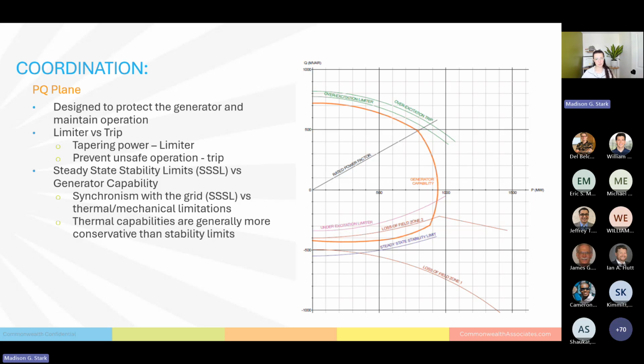What we do is we start here at unity power factor, and then we push out. And that's how we test coordination of our system. So starting here and going up, we're moving into our overexcited territory. We're pushing VARs into the grid. We're supplying a lot of power. So what does this look like? Well, the first thing we're going to hit is our generator capability. That's good. Steady state capability, we can sustain this indefinitely.